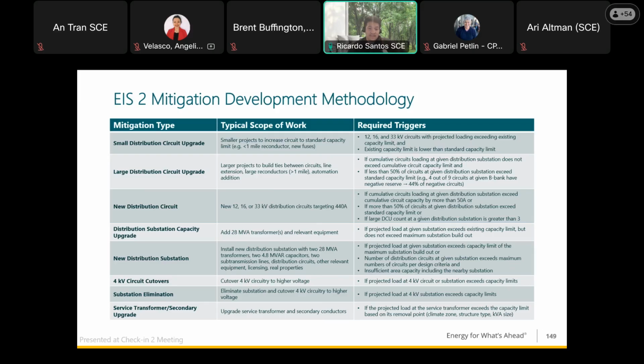The reason we chose 50% is based on estimates of average large distribution circuit upgrade cost compared to new circuit cost, as well as our average circuit count in a substation. For instance, an average large DCU cost is around $800,000 and a new circuit cost is around $3.2 million. In the example with 4 of 9 circuits above capacity, this is right at the brink of the new circuit cost, since 4 times $800K is around $3.2 million. However, if it were 5 circuits above the loading limit, that cost might be higher than building a new circuit, so the script would propose a new circuit instead.